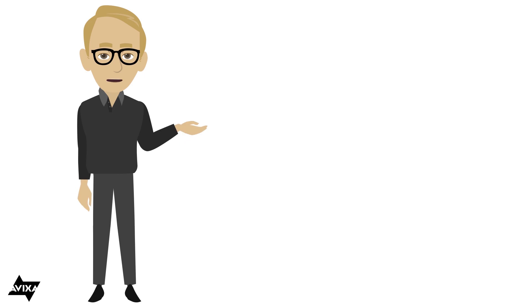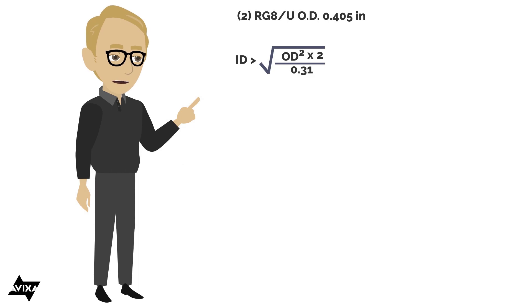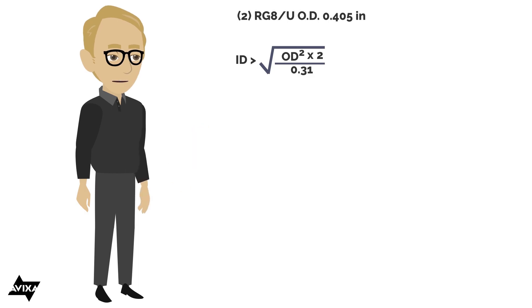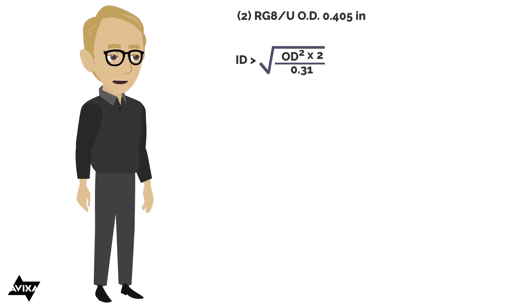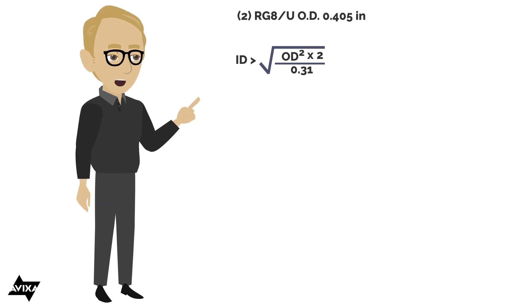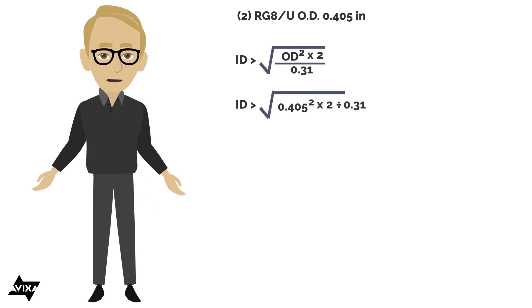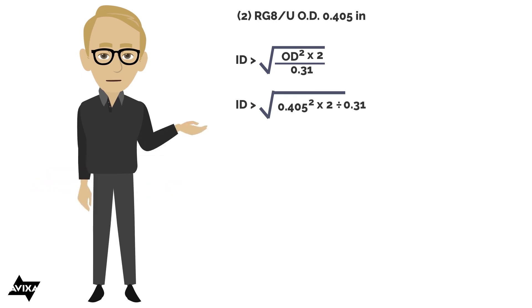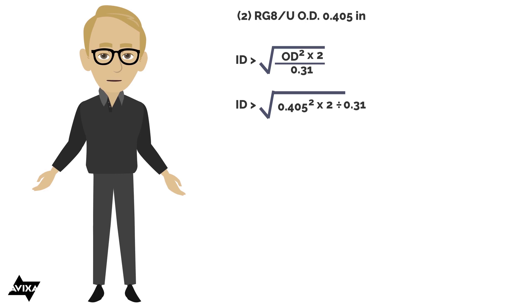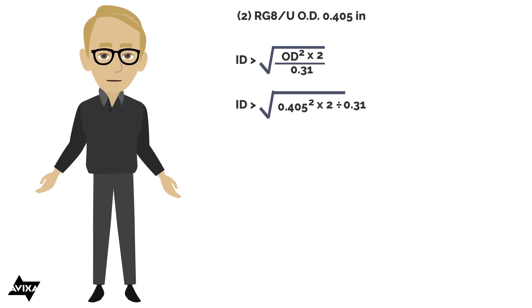Let's do a couple more problems with conduit capacity. This time I'm doing a couple of coax cables, and they're each 0.405 inches outer diameter. Since I'm only doing two, my fill percentage is going to change — in this case it's going to be 0.31, or a 31% fill. The inner diameter of the conduit I need must be larger than the square root of 0.405 squared times two, divided by the fill percentage of 0.31.